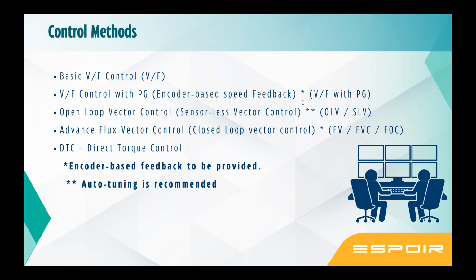In the dynamic auto tuning, it gives a much better result. I can explain that factor later, how it is done. Now, if you cannot disengage these aspects, you can just do the basic auto tuning where the motor shaft doesn't turn. It will just heat up the system and then see certain parameters. It injects certain voltage and then sees how the return current is. Accordingly, it develops its mathematical model.